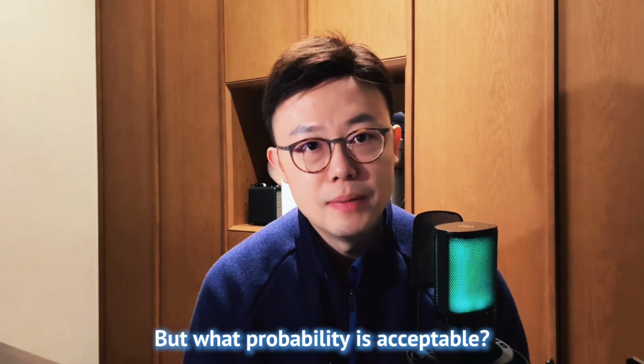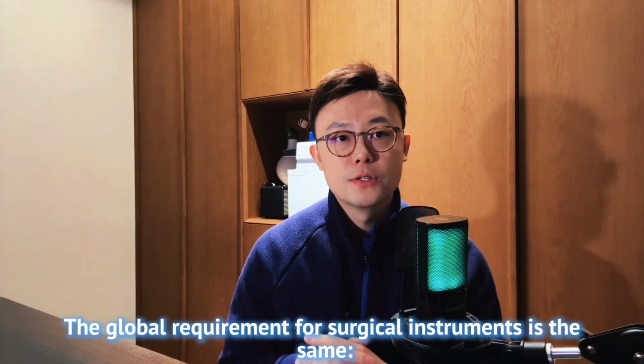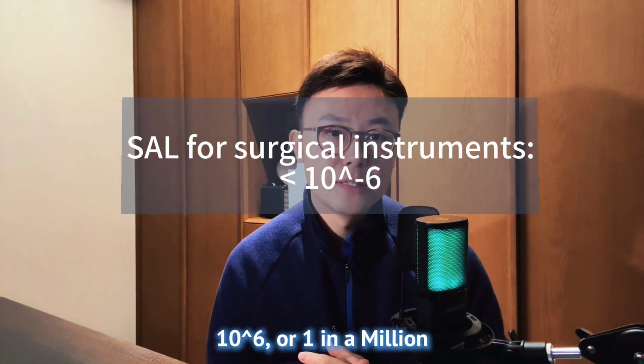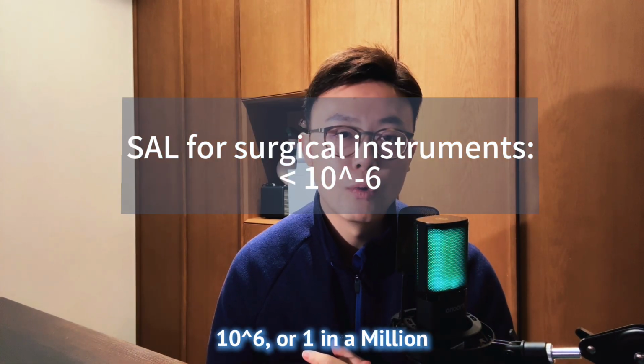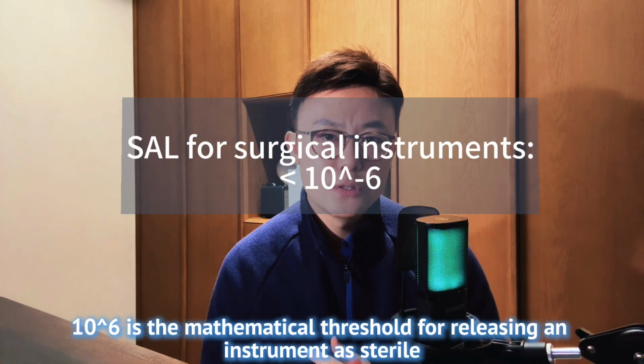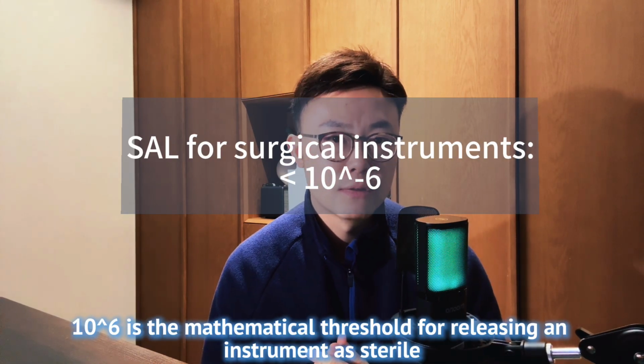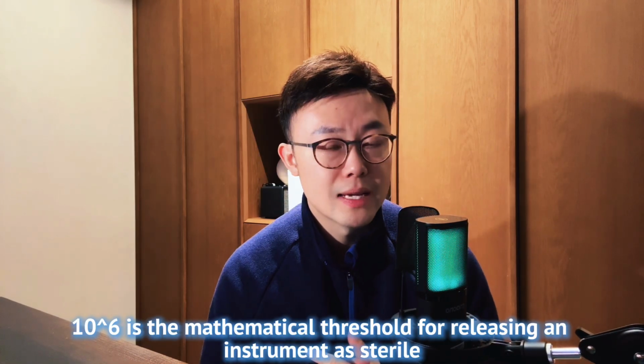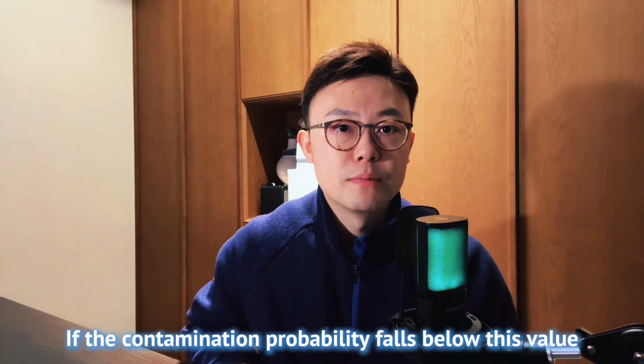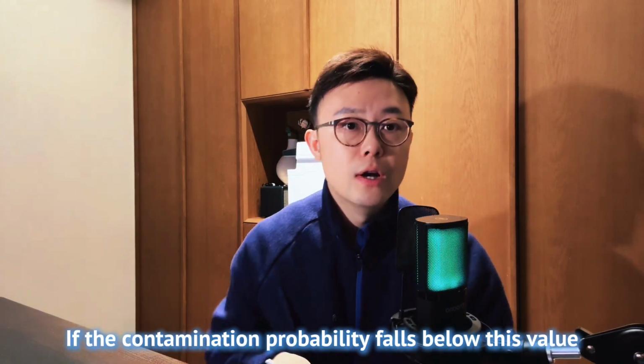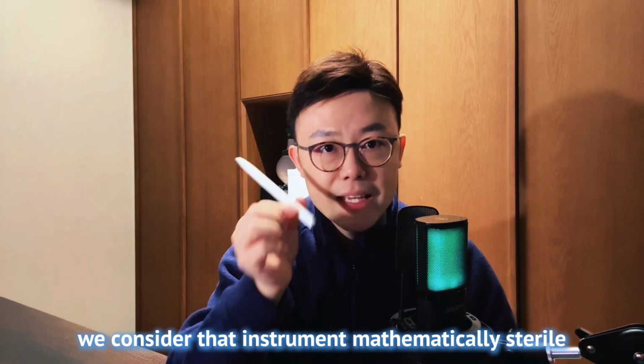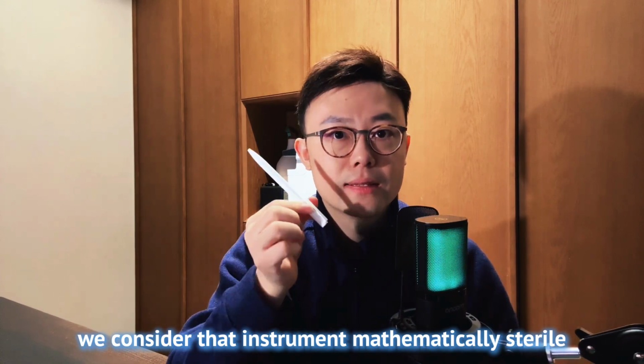But what probability is acceptable? The global requirement for surgical instruments is the same: 10 to the power of minus 6, or 1 in a million. 10 to the minus 6 is a mathematical threshold for releasing an instrument as sterile. If the contamination probability falls below this value, we consider that instrument mathematically sterile.